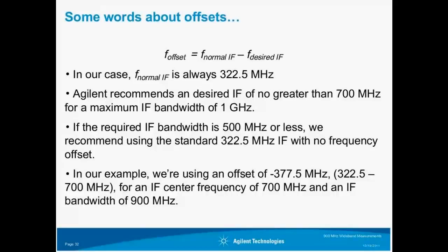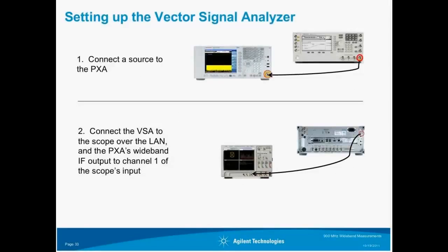Let's briefly discuss offsets. In our case, the normal IF is always 322.5 MHz. Agilent recommends a desired IF of no greater than 700 MHz for a maximum IF bandwidth of 1 GHz. If the required IF bandwidth is 500 MHz or less, we recommend using the standard 322.5 MHz IF with no frequency offset. In our example, we are using an offset of minus 377.5 MHz for an IF center frequency of 700 MHz and an IF bandwidth of 900 MHz. Once you've connected your source to the RF input of the PXA and the IF output to the scope, connect your vector signal analyzer to the scope if it's running on a separate computer, or simply use it on the scope directly.